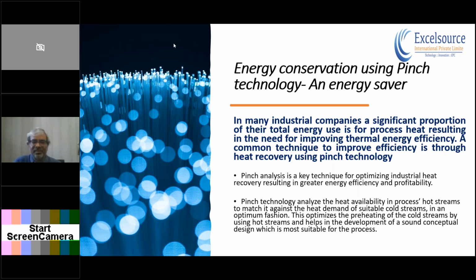So pinch technology analyzes the excess heat availability in the process hot streams to match it against the heat demand of suitable cold streams, in an optimum fashion, by preheating the cold stream using the hot stream, and it helps the development of a sound conceptual design which is most suitable for the process. We have to adapt this process so that it is suitable for that particular process. I'm just going to give you an example of an edible oil refinery where we have done this. It is not that the same concept will be utilized in a different industry. Even in the same industry it can change, and we have to study the plant. But yes, the concept remains the same.